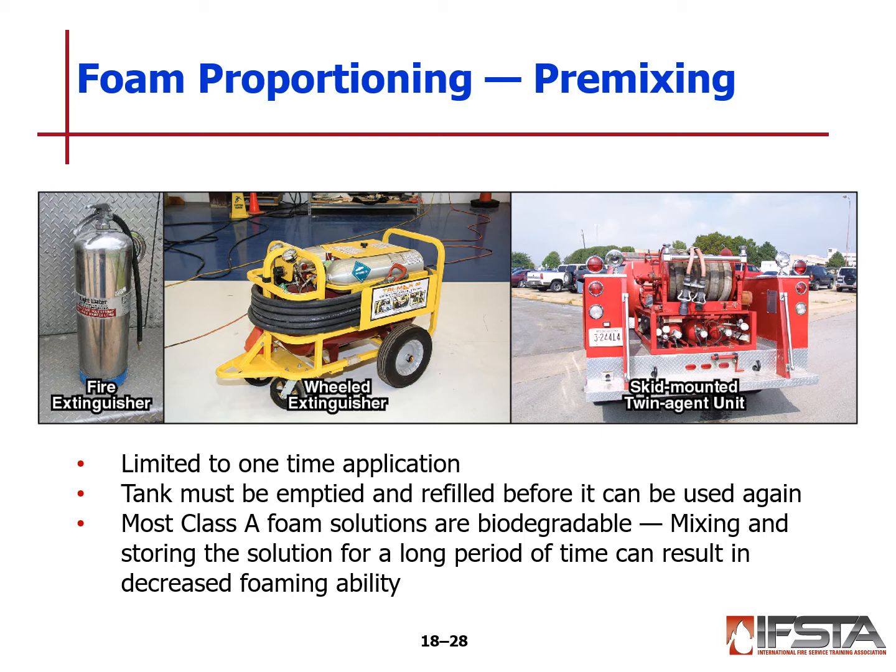Foam proportioning and pre-mixing, limited to one-time type application. The tank must be emptied and refilled before it can be used again. Most Class A foam solutions are biodegradable, and mixing and storing the solution for long periods of time can result in decreased foam ability. So a lot of pre-mixed tanks on these solutions or wetting agents, we will dump the solution in the tank ahead of time, and this could be right before we apply it.